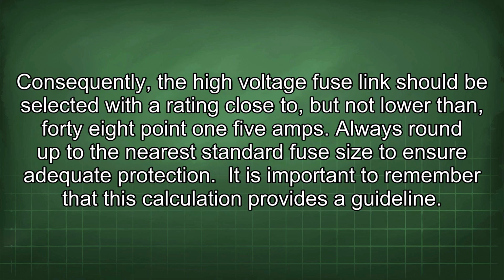Consequently, the high voltage fuse link should be selected with a rating close to, but not lower than, 48.15 amps. Always round up to the nearest standard fuse size to ensure adequate protection. It is important to remember that this calculation provides a guideline.